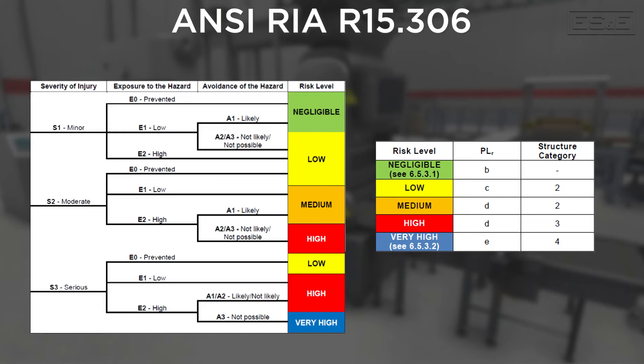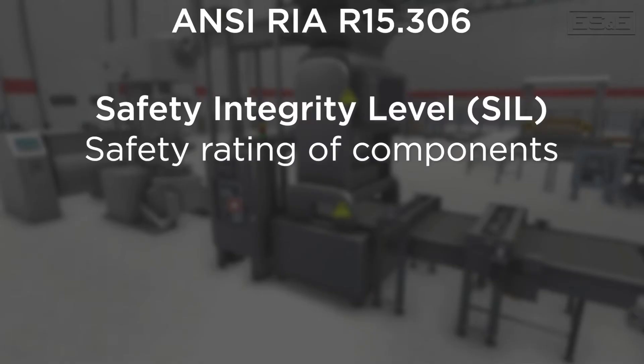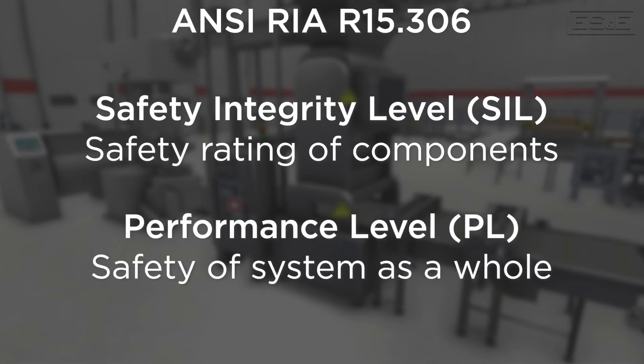Once the assessment is completed and the risk level is identified, you can quickly move to determine the category rating the system needs to be designed to, as well as the performance level that will need to be attained when the system is implemented. For people who are not familiar with safety, a simplified way of understanding a category is the way that the system is designed. A safety integrity level, or SIL, is the component's safety rating, and a performance level is what is achieved after the system is designed and installed with the proper SIL-rated components.